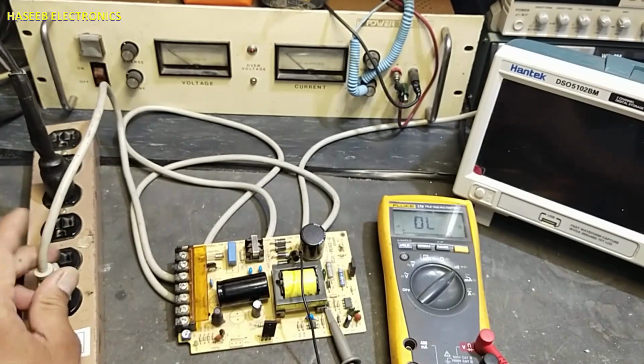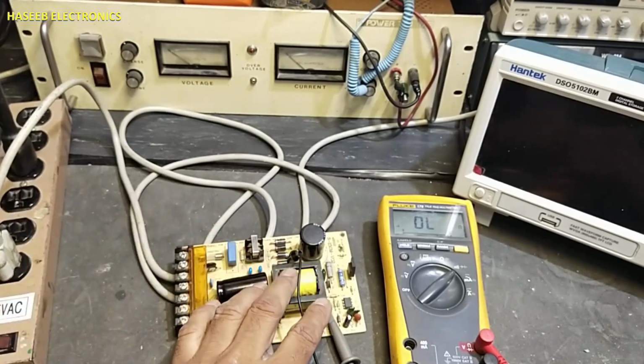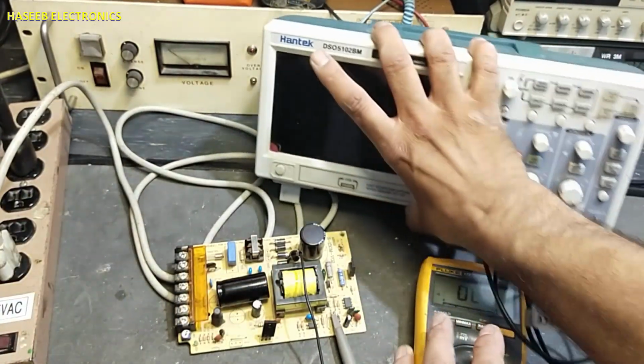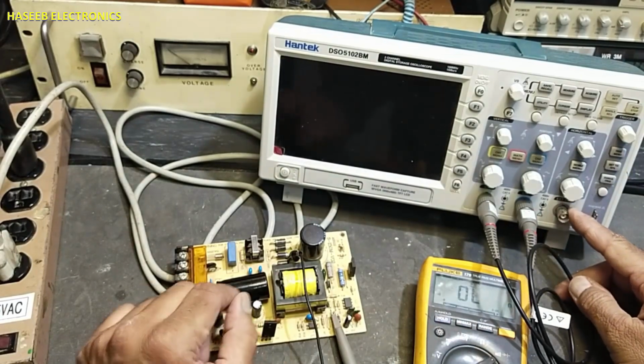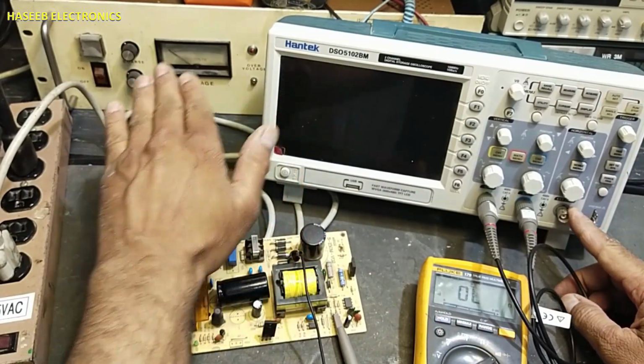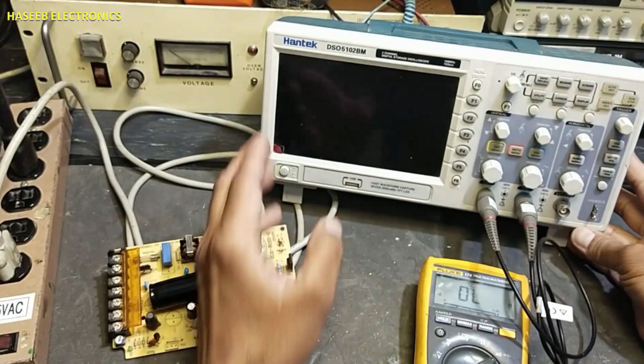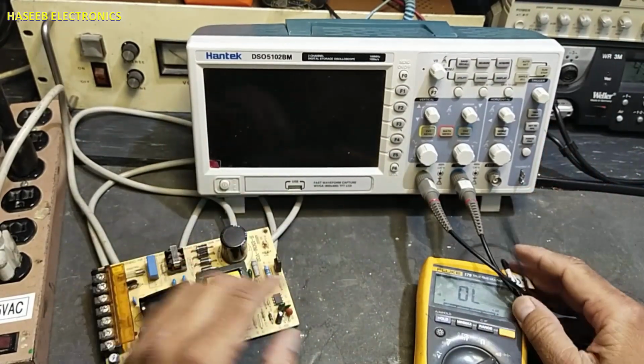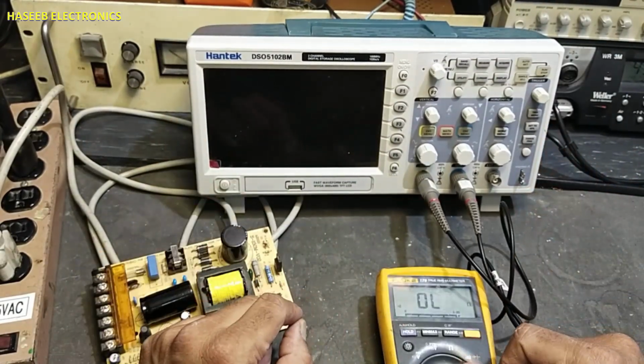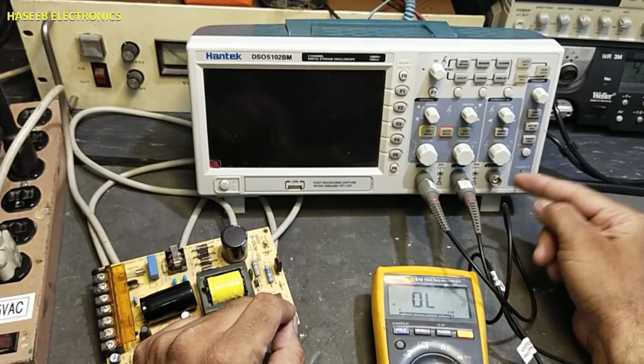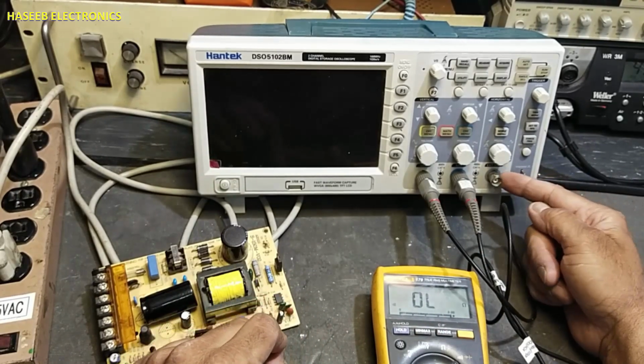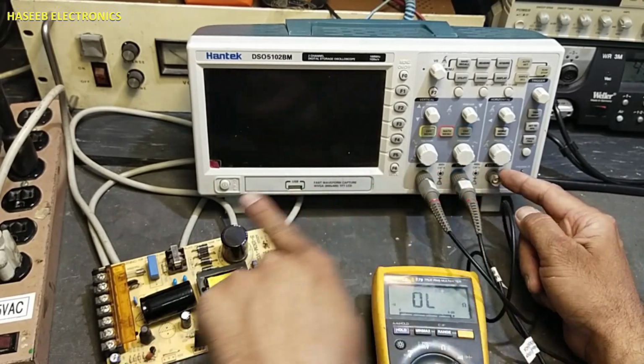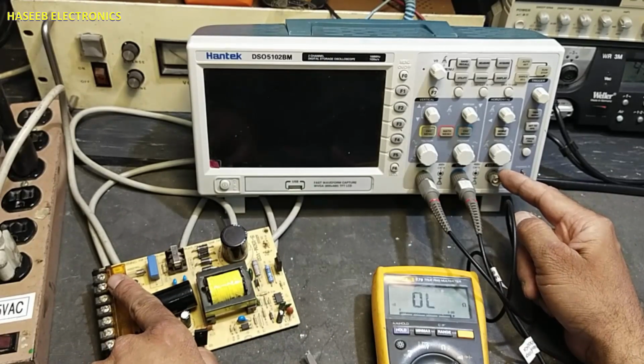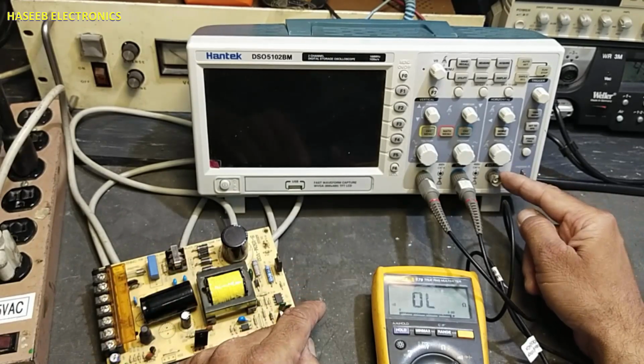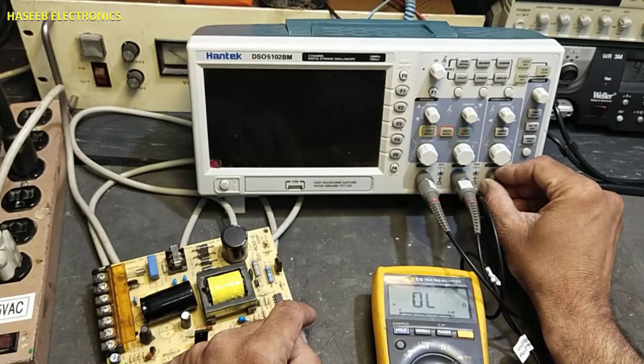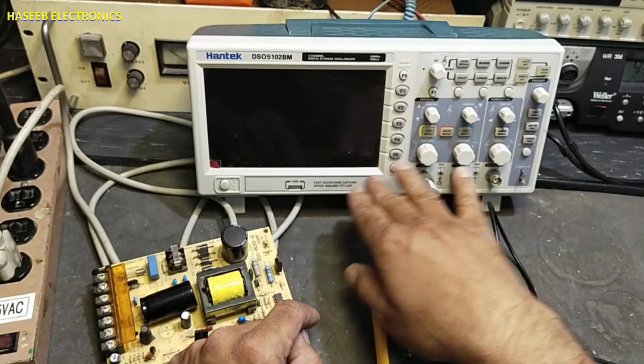Otherwise, our line voltage will appear in the ground terminal and also the chassis of other equipment. If you are testing any unisolated signal, be careful. This ground terminal is directly exposed to line voltage. Never touch any ground terminal, never touch any probe.